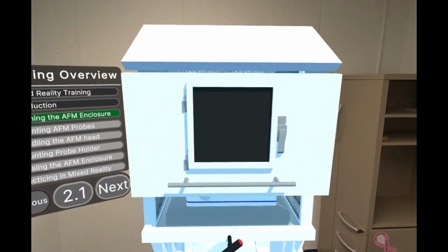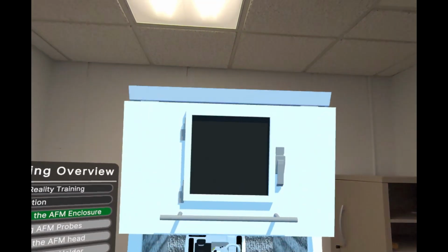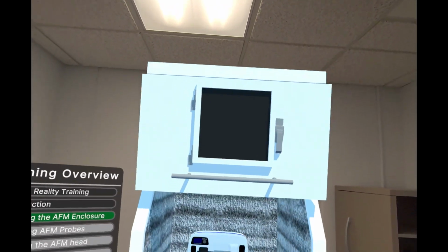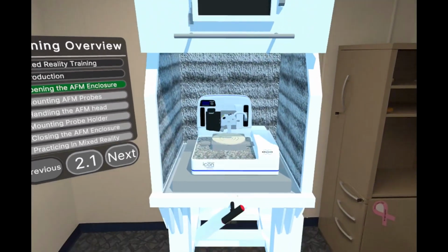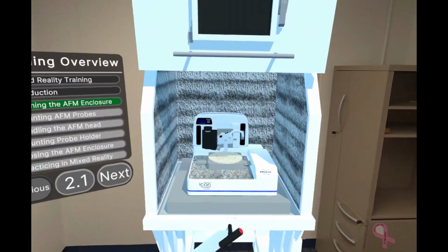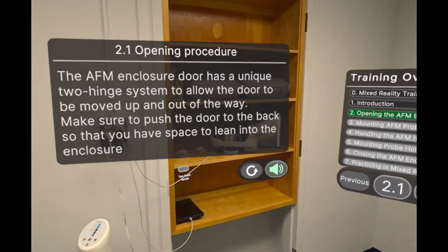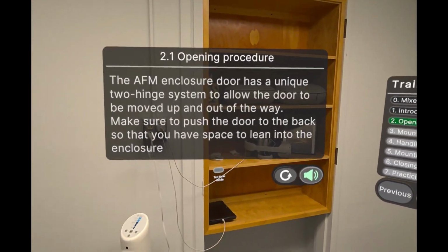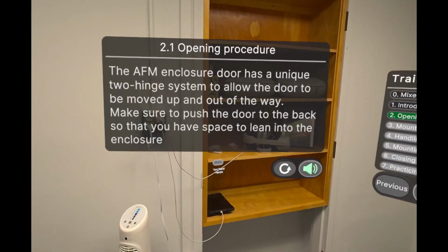Be careful not to let the door bump into the soundproofing strips on the way up. Once the door is opened, remove the Allen key from the lock and lay it inside the AFM enclosure beside the AFM on the left-hand side of the air table so that you're not bumping into it.